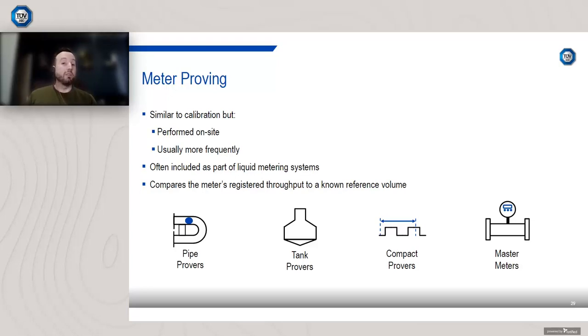Provers are often included as part of liquid metering systems. What is a prover doing, or what are you doing when you prove a meter? You're comparing your meter's registered throughput to a known reference volume. Now there's various different types, designs and styles of prover. You've got pipe provers, tank provers, compact provers, which are another form of either a pipe or a tank prover, and you've got master meters. I'm not going to focus on every single type of prover, but I'm going to talk about a few of them in the next few slides.